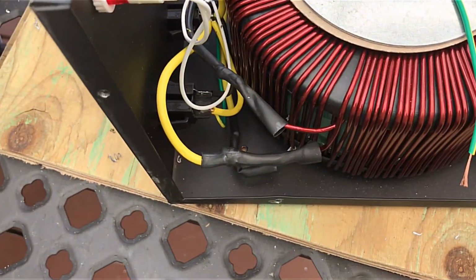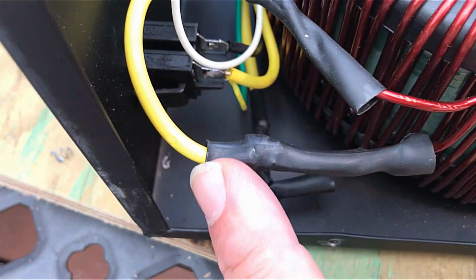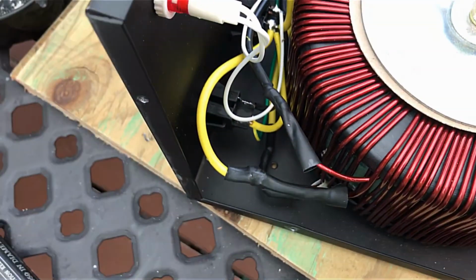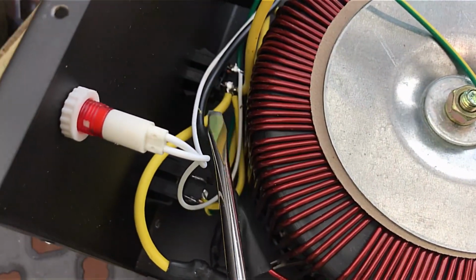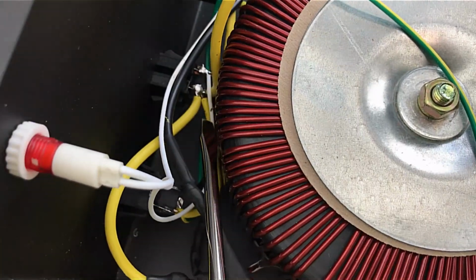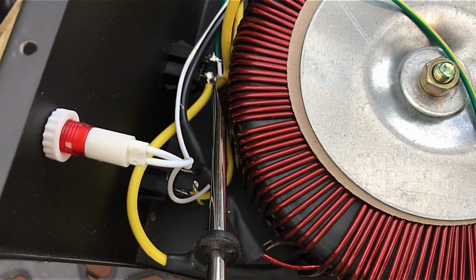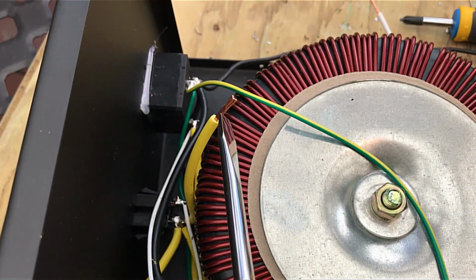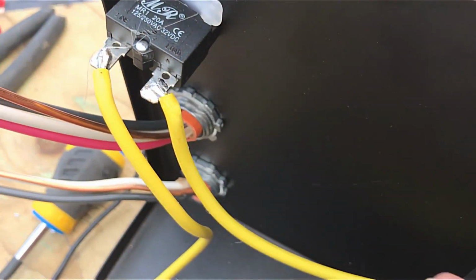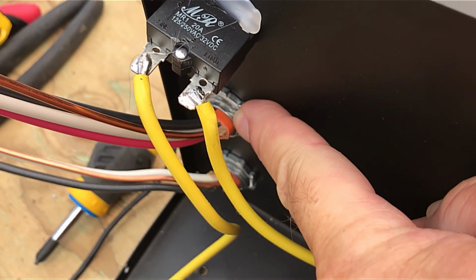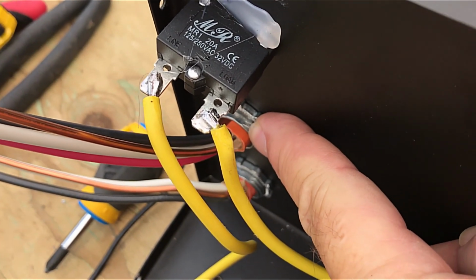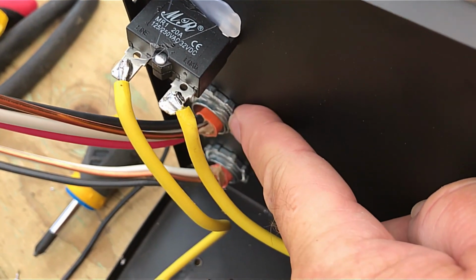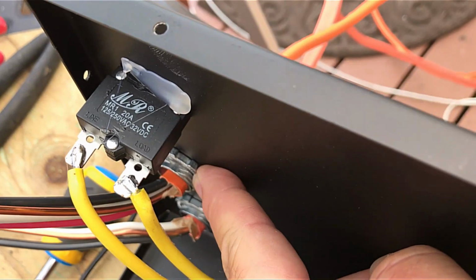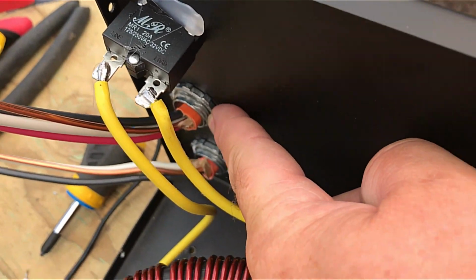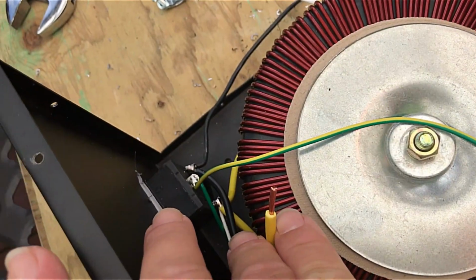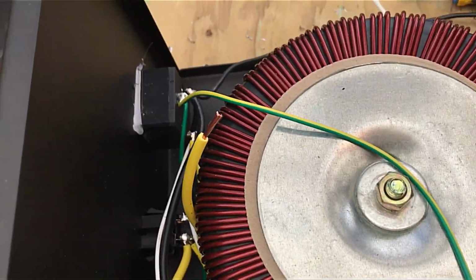Okay, I got to thinking that there might be some people wondering how I come off of this center tap out of this transformer. You can see that this yellow wire right here goes down to this outlet here, and several wires come off of that, and those are all neutral. Well, this one right here is the one that I've tapped into. I cut it off because it did go to another breaker that was down here. If you use this box for 110 volt input and step up to 220 volts output, that's what this breaker protected. Since we're never going to have that scenario, I've got it wired so that that's not even used, but the wire that I cut out of that is the neutral for this, so that's what I'm using.